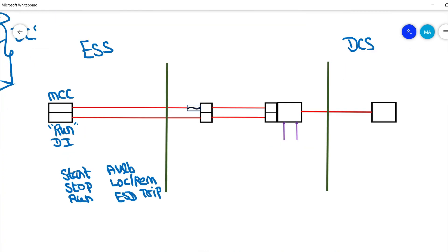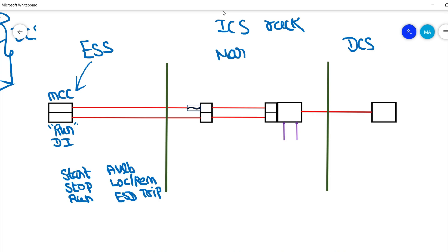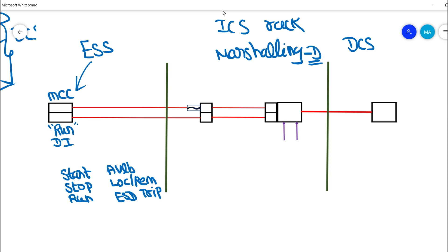Now you have an idea of what MCC is. This run feedback is considered a digital input to DCS — we have already discussed digital input in a previous video, and the link will be in the description. From the MCC panel we take this run feedback to the ICS rackroom. This is the marshalling panel — specifically a digital marshalling panel — where all digital inputs are terminated.